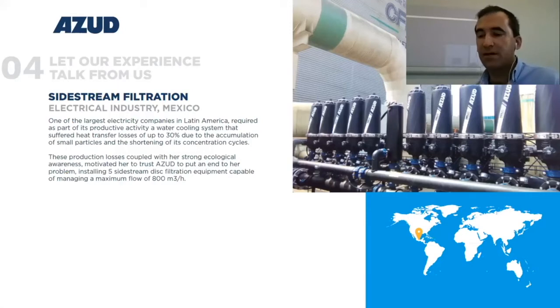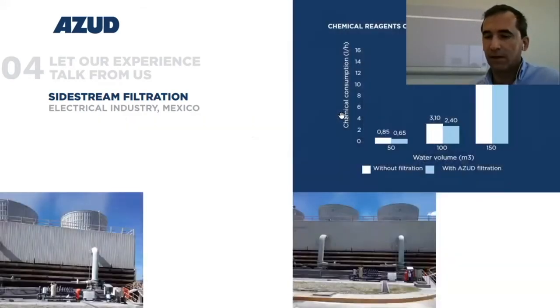So the main problems here that we were facing were the high chemical consumption, and the fact that it was not possible to maintain a constant water quality. With all these problems, AZUD was contacted to improve the performance of the refrigeration system. Our proposal was a Sidestream filtration for each system of 10% of the total volume at 50 micron. This way, we managed to maintain TSS levels below 5 ppm by removing the suspended solids.